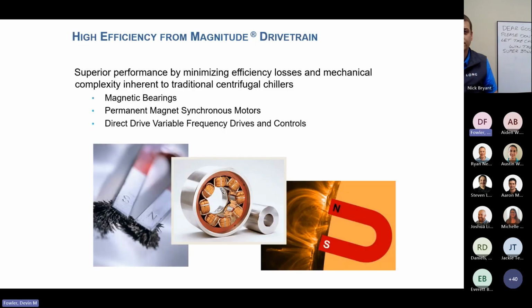So with our Magnitude products, we're going to deliver a high efficiency drivetrain. We're going to increase our performance that we would traditionally see with an oiled centrifugal product. We do this in a couple of ways. First is going to be magnetic bearings versus oiled bearings, so we don't have any bearing losses or contact losses, and it's also going to be a little bit quieter because of those no contact bearings.